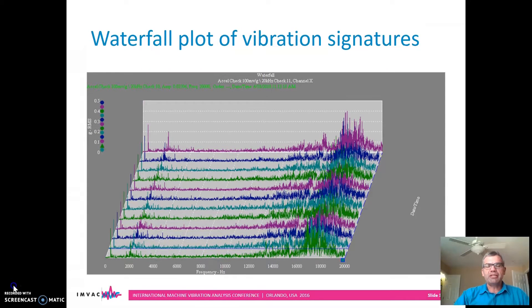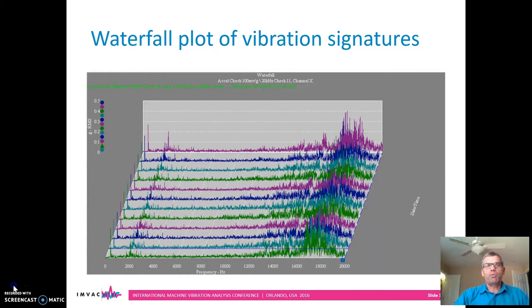The condition monitoring team was in agreement — this motor wasn't doing well. Just see how the amplitudes of the higher frequencies are growing as this data was taken on consecutive days. The question was: when should they take action to avoid costly downtime without wasting too much of the motor's residual life?